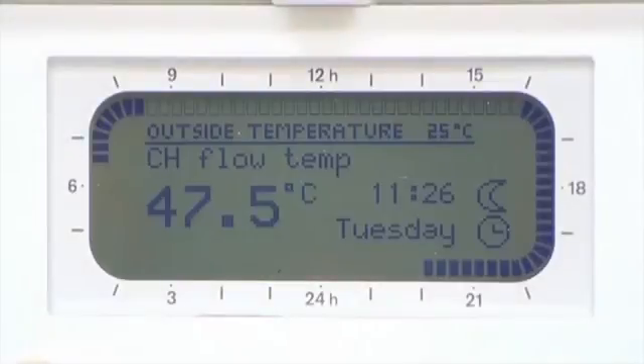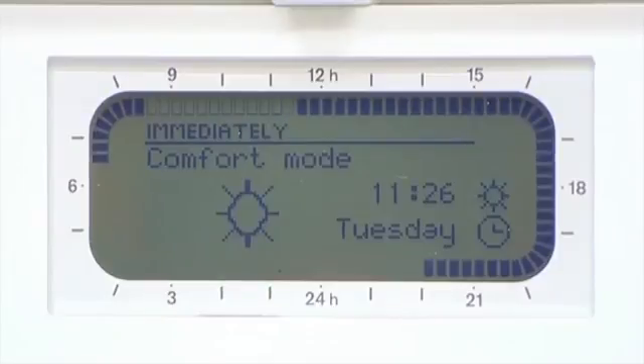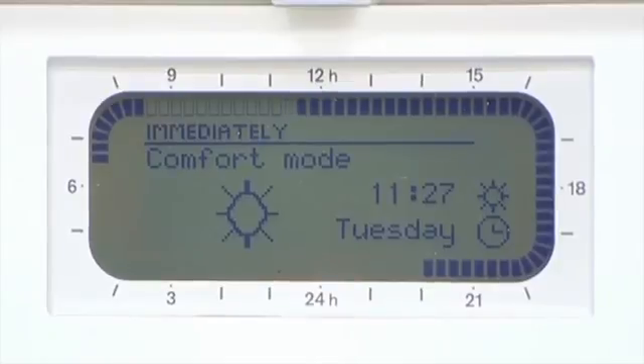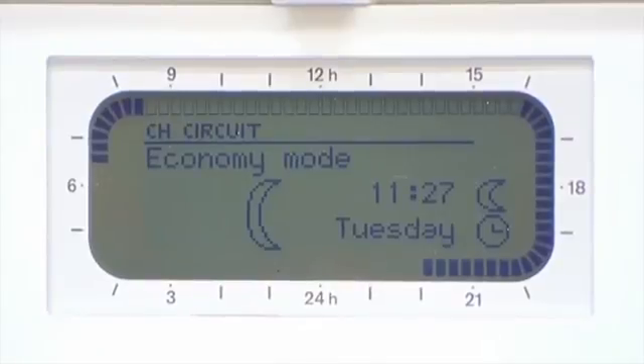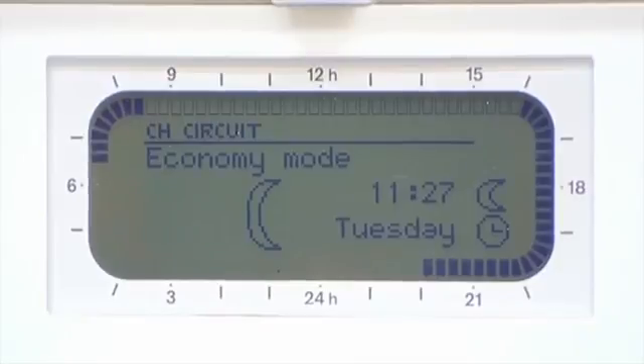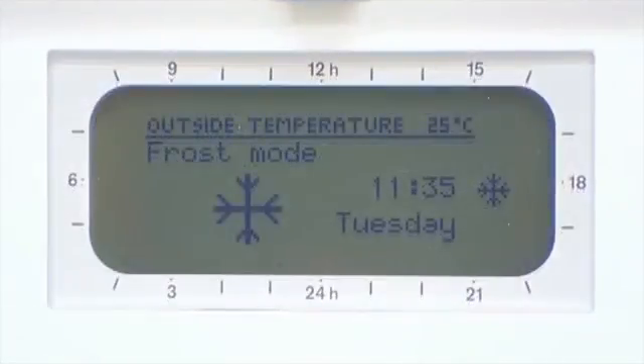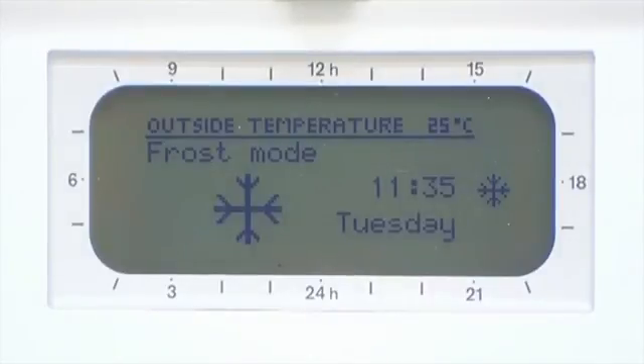There are three main temperatures that the programmer works to, and these are factory set but can also be changed by the user. Comfort: this is regarded as the daytime on period temperature, around 21 degrees as an example. Economy: this is normally regarded as an off period for your central heating, or a background temperature of around 15 degrees Celsius. Frost: this is generally used when the property is unoccupied to avoid freezing, around 5 degrees Celsius.